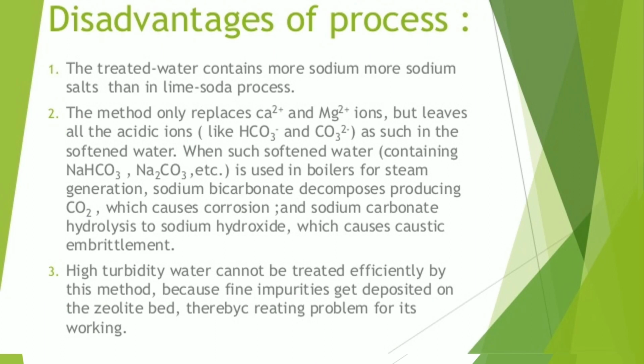At last, we discuss the disadvantages of this zeolite process. The first disadvantage is that the treated water contains more sodium, more salt, than in the lime soda process. The second disadvantage is that this method only replaces calcium and magnesium ions but leaves all the acidic ions like bicarbonates and carbonates as such in the softened water.